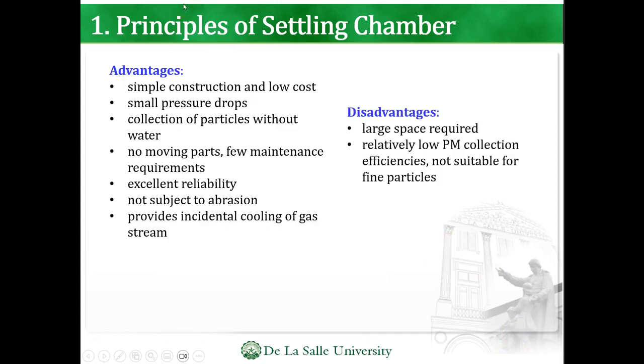The advantages of settling chambers are that they are simple and easy to construct, and the cost is low. There is a small pressure drop, collection of particles without water is possible, no moving parts, few maintenance requirements. They are reliable, not subject to abrasion, and provide incidental cooling of the gas stream. Disadvantages include requiring a large space and relatively low particulate matter collection efficiencies, which is why this is usually done before the main air pollution control devices.